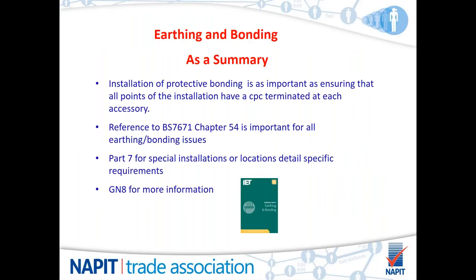Okay, so as a summary then, the installation of protective bonding is as important as ensuring that all points of the installation have a CPC terminated at each accessory. You could make reference to BS 7671 chapter 54. This is important for all earthing and bonding issues. You could also reference part 7 for special installations or locations detailing specific requirements, or guidance note 8 for more information. Well, I do believe the other guidance notes as well, guidance notes will assist you in any earthing and bonding questions you may have.